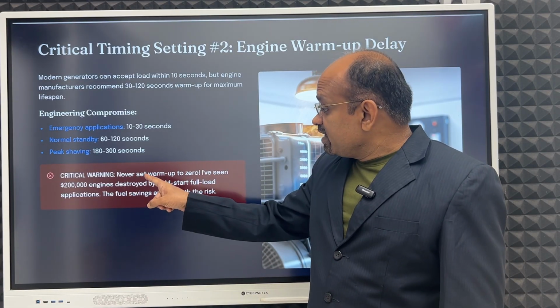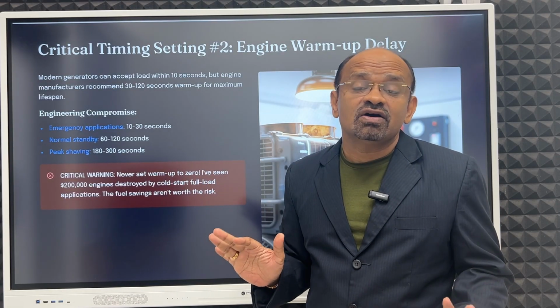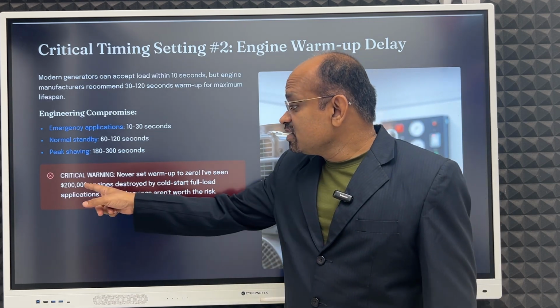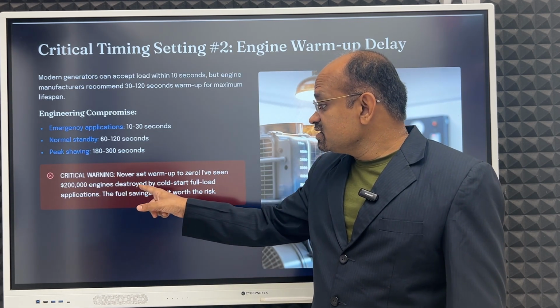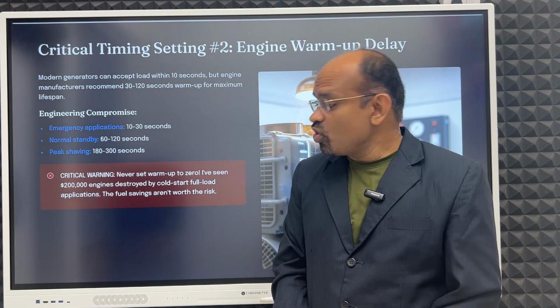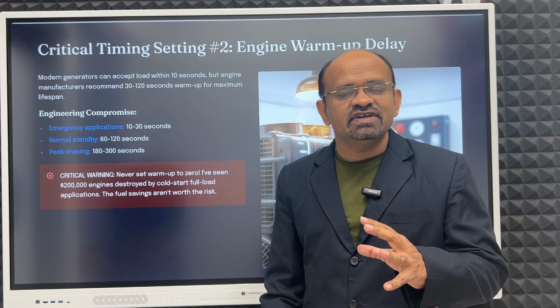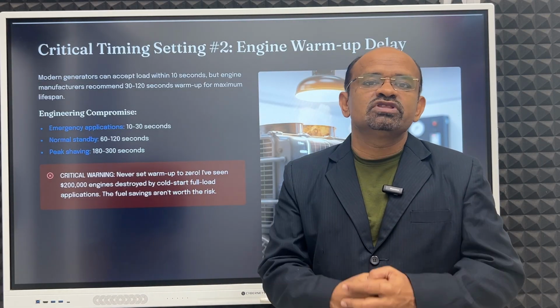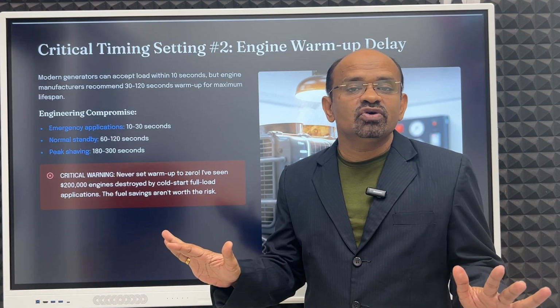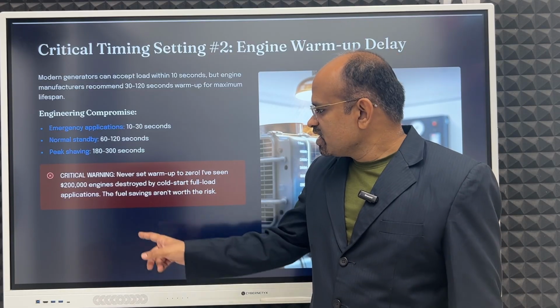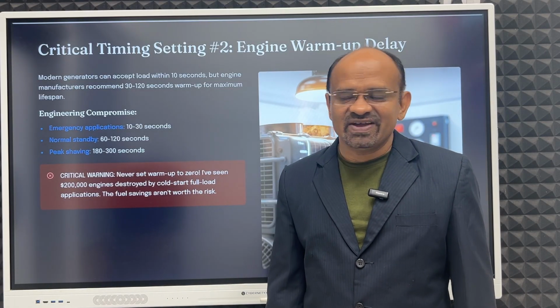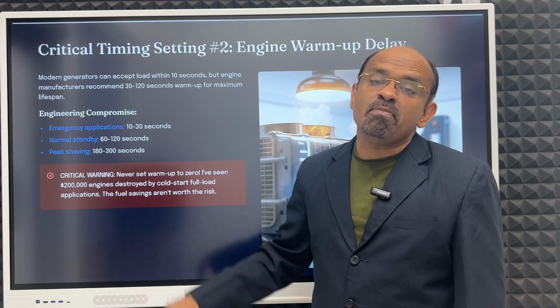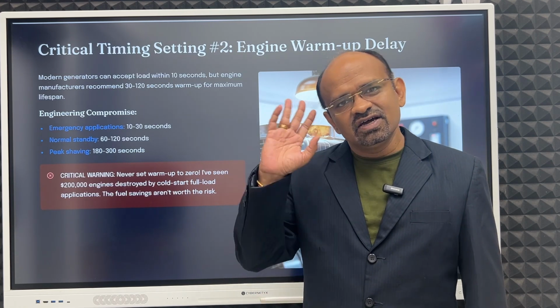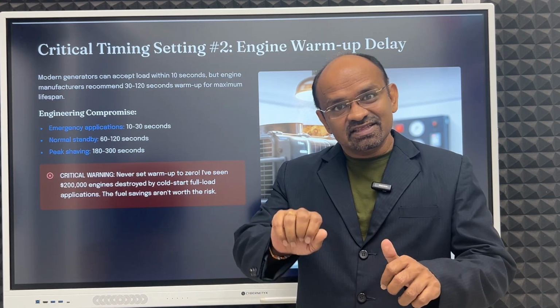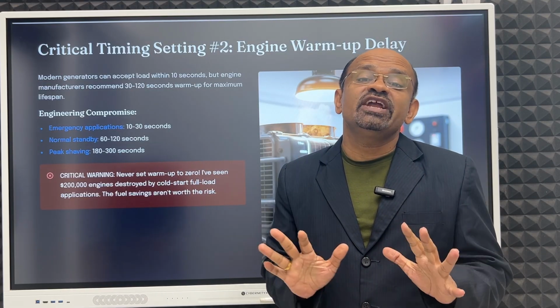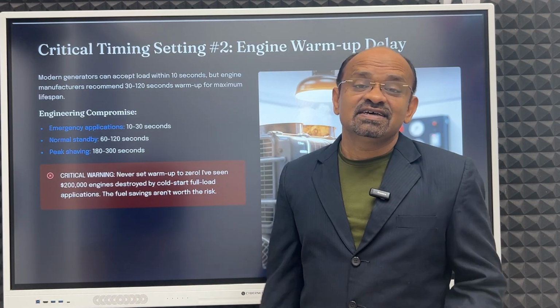Critical warning: never set warm up to 0, never. Otherwise what will happen? I have seen a 200,000 USD engine destroyed by cold start. For full load applications at cold start, if it is not warmed up properly and you just put the load on at 0% warm up, then it is gone. Your engine will not serve you, it will be damaged. So the fuel saving isn't worth the risk. It is okay if some fuel is burned in this warm up. Warm up is very important. That is the reason in the old days we used to turn on the heater first, then start the engine of our cars, wait for some time, and then put the gear. This is the engine warm up.